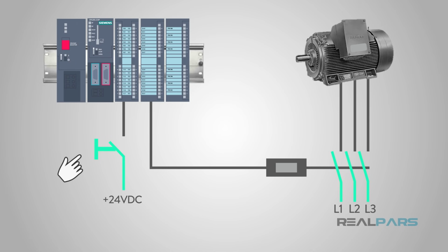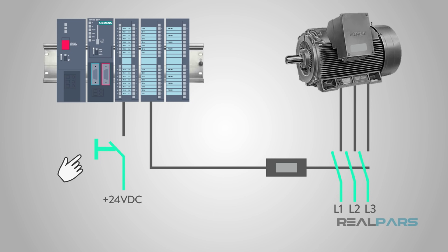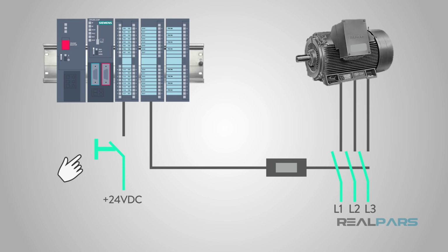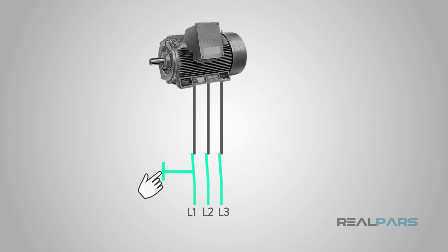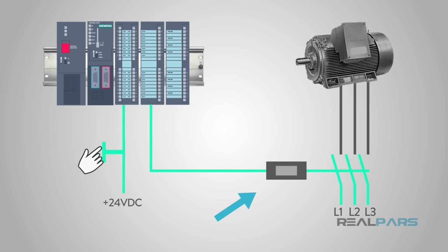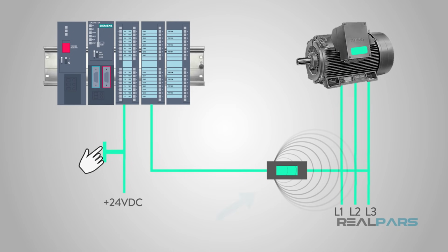A very common reason, especially in an industrial setting, is for voltage and current requirements. Many machines and equipment use a higher voltage to run. To make it safe for the operators, we use a low voltage and current for our controls. You wouldn't want someone pushing a button with high voltage attached to it. I know I wouldn't want to on a regular basis. It takes a very low amount of current to cause bodily harm. Plus, most push buttons and switches are rated for fairly low current. When we use a relay, the contacts that close can be rated for much higher current.